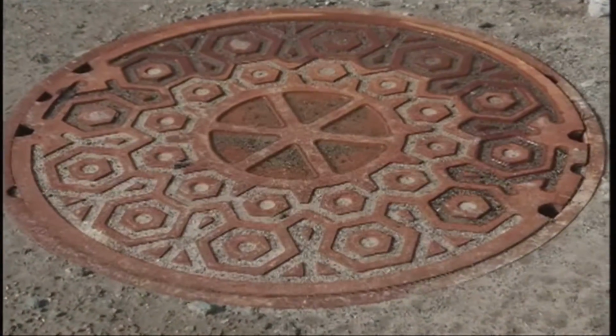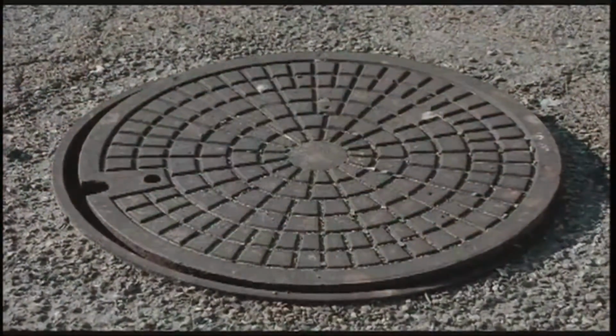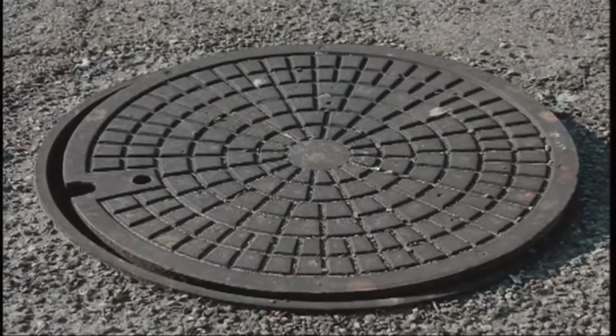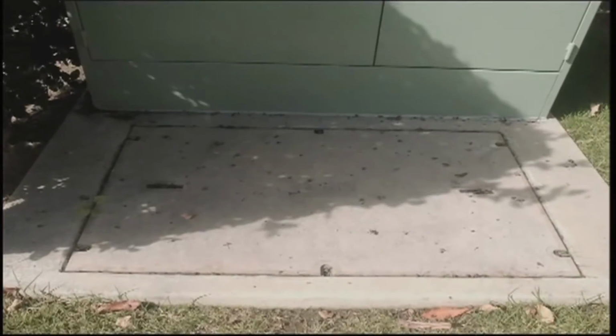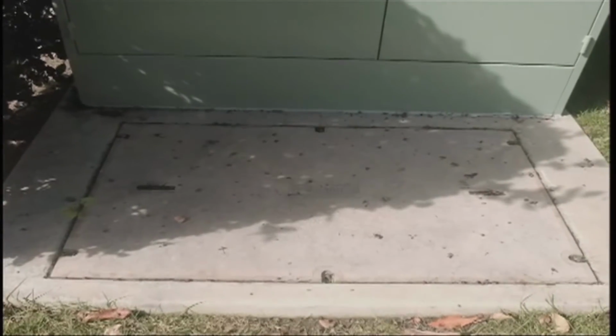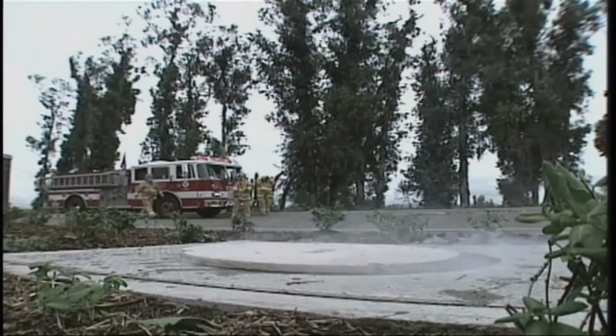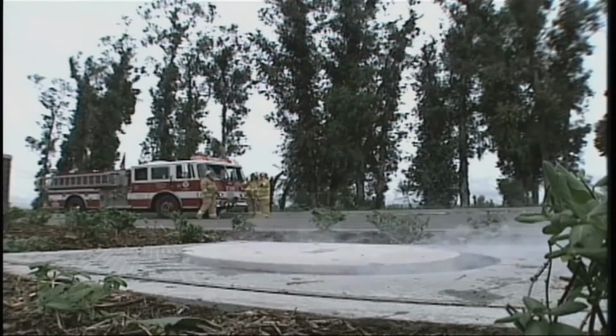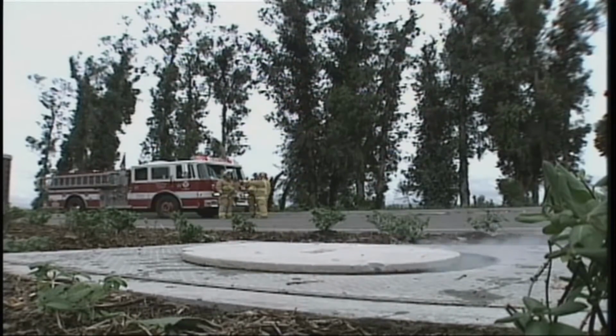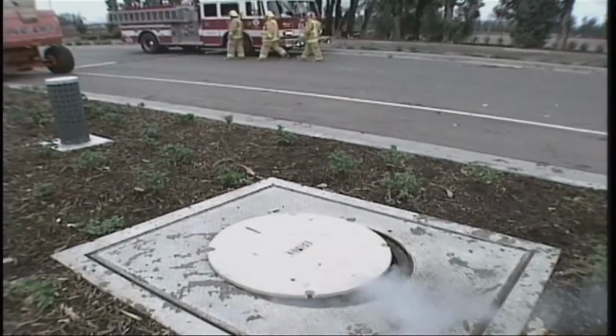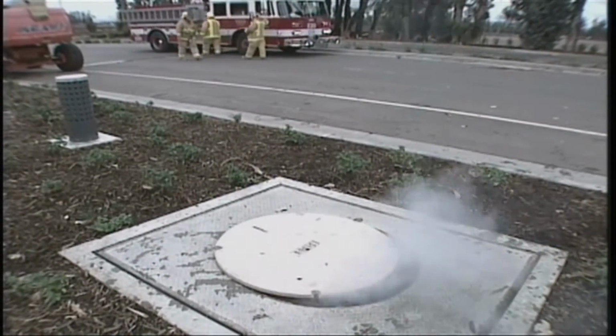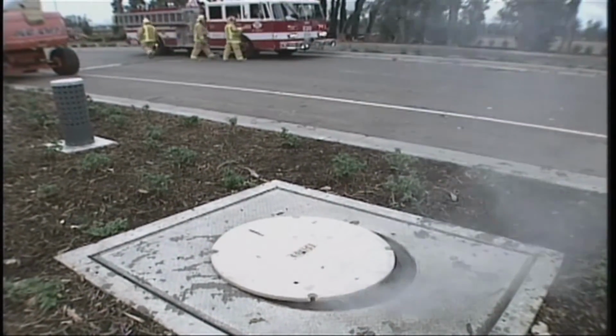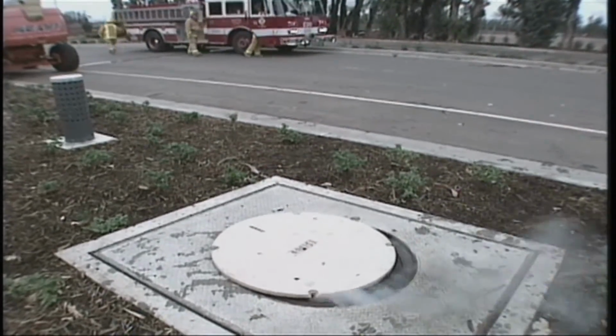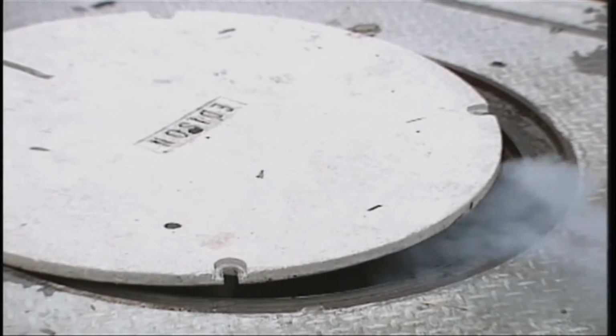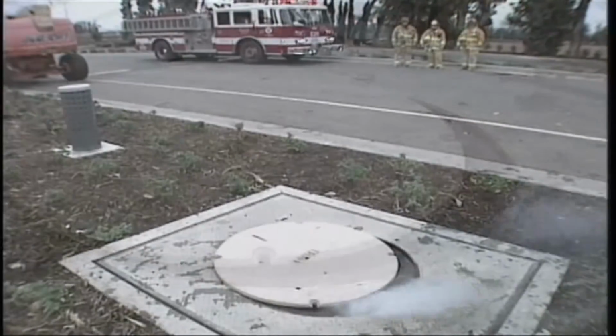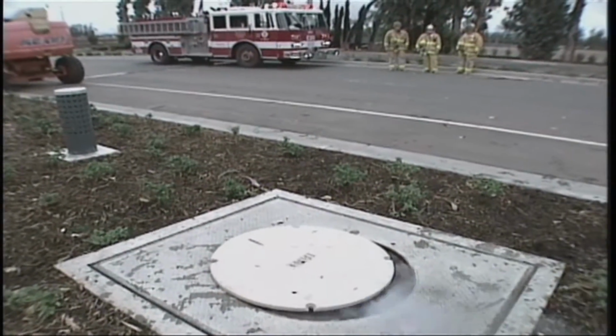Emergencies involving underground manholes or vaults are high-risk situations for first responders, even if the appearance above ground is benign. If flammable gases are present in the manhole, removing the cover could provide enough oxygen or sparking to cause an explosion. If gases are present in the cable ducts that run from manhole to manhole, there could be additional explosions in adjacent manholes. If an underground transformer in the vault has failed and the oil is above the ignition temperature, it could explode without notice.